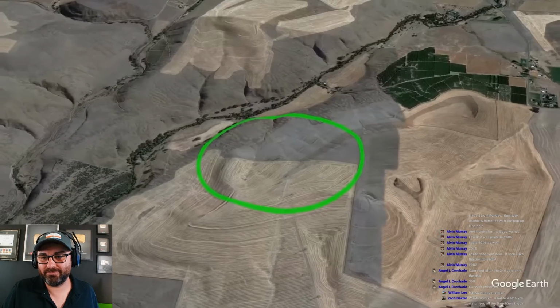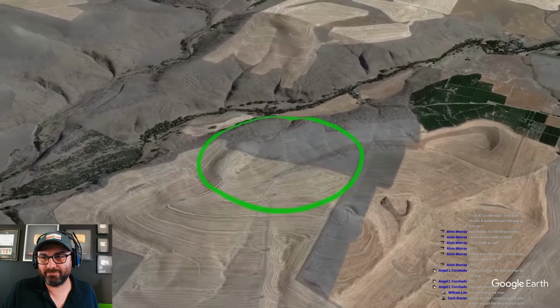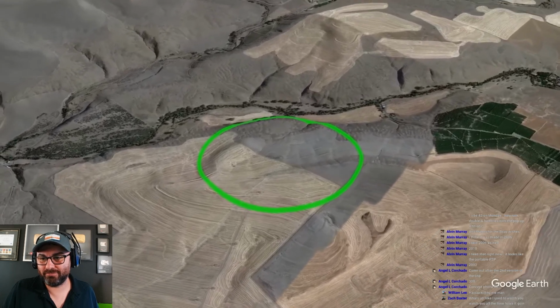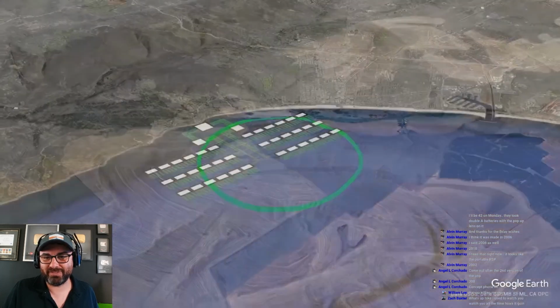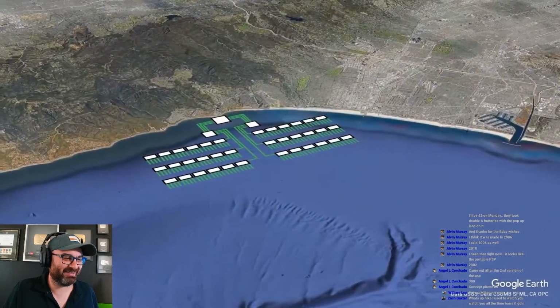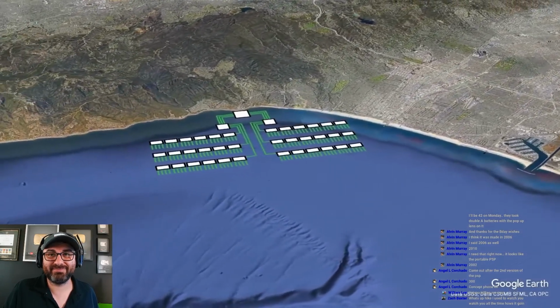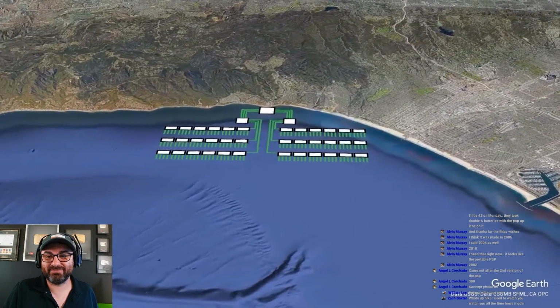In Oregon, over 1,000 electrodes are buried in a ring with a circumference of 2 miles or 3.2 kilometers. In California, the grounding system consists of huge electrodes submerged in the Pacific Ocean a few miles off the shore. Unlike AC return currents that generally follow a path that matches the transmission line, DC currents can flow through the entire Earth. In essence, the electrodes are completely decoupled. That does mean they're susceptible to some environmental issues, though.